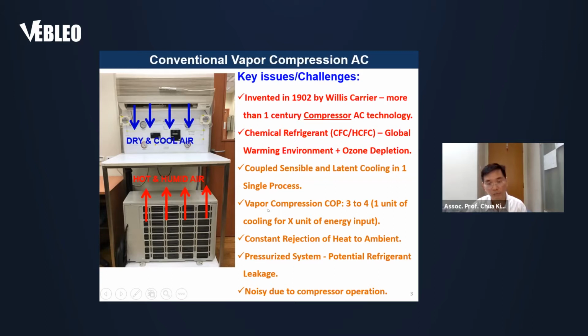In terms of performance, the vapor compression cycle has a coefficient of performance, or COP, of about 3 to 4. The higher the value, the more efficient your system is. For example, Daikin and Mitsubishi air conditioning systems, well known in the world for being very efficient, have a COP within this range.